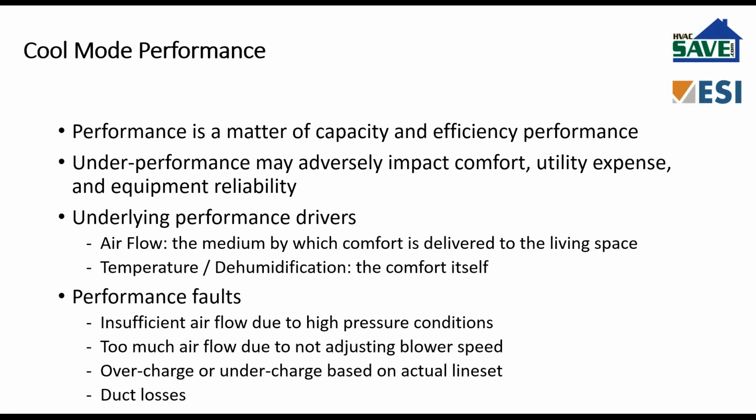Or perhaps it's getting there, but not at the volume that it needs to be. Okay? So insufficient airflow. Too much airflow is also a fault. A frequent fault, okay? Nowadays, these blowers oftentimes ship out as a default on high speed. High speed may not be appropriate, and in fact probably is not appropriate for the needs of that outdoor unit.